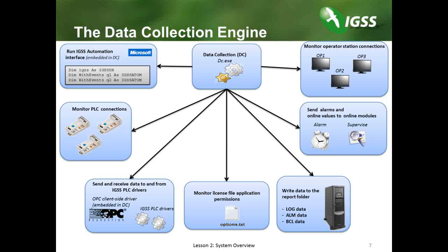The data collection engine also ensures that the number of objects configured for the system are present in the license file — called Options Text on our system. Data to and from IGSS PLC drivers is sent and received by the DC engine. Among the drivers, we have OPC client-side drivers and, of course, OPC server functionality embedded in the DC engine. The DC engine also ensures that PLC connections are stable and running, and ensures the running of the automation interface, for example if VBA code is included in the project. As you can see, the data collection engine is one of the backbones of the IGSS system, and the DC must be running for IGSS to function.